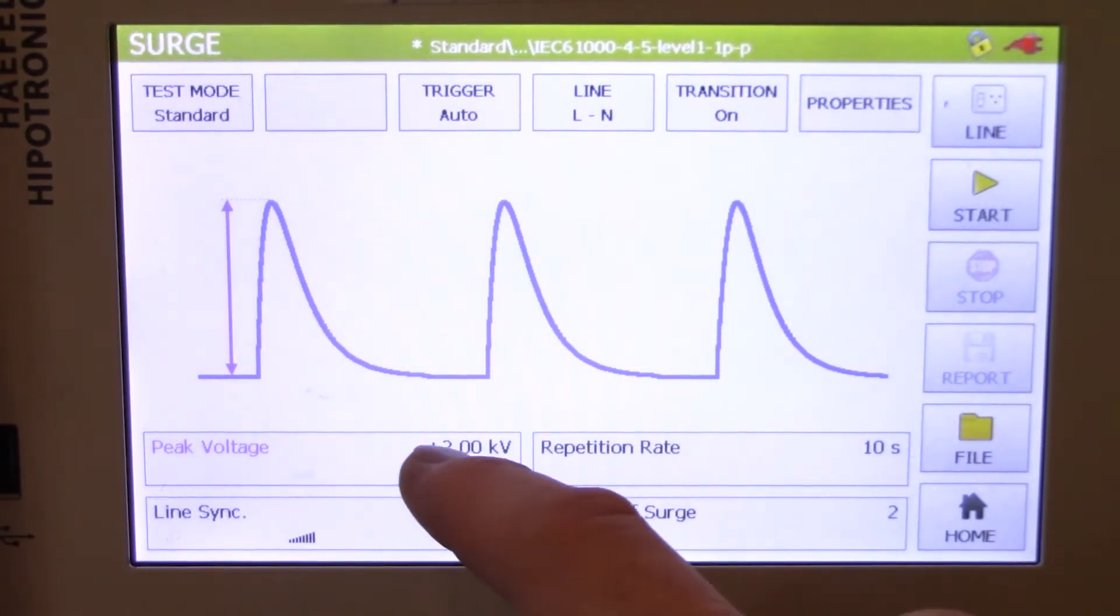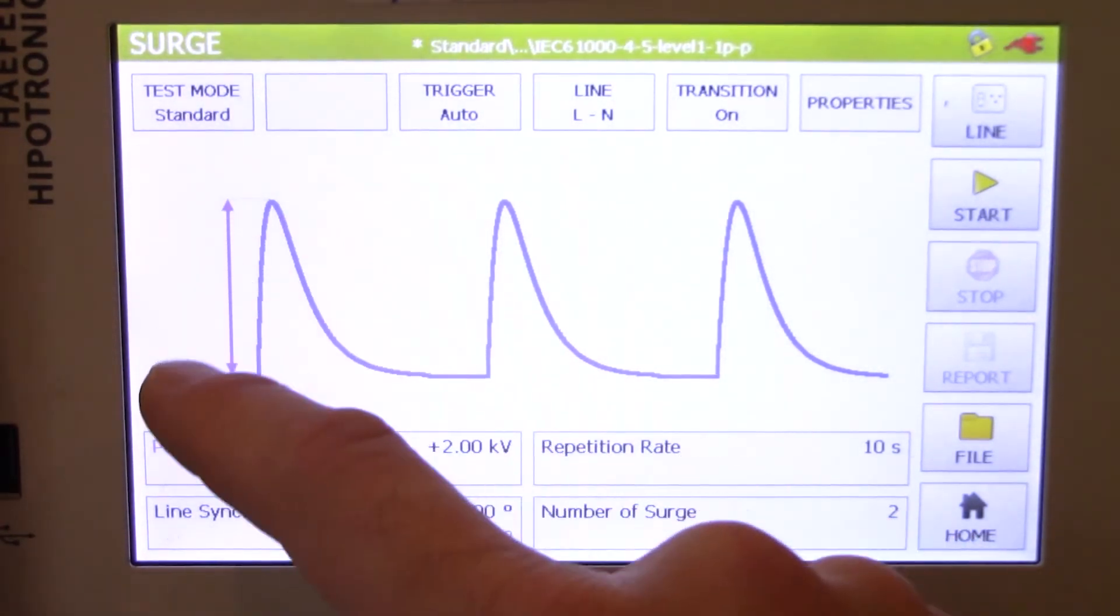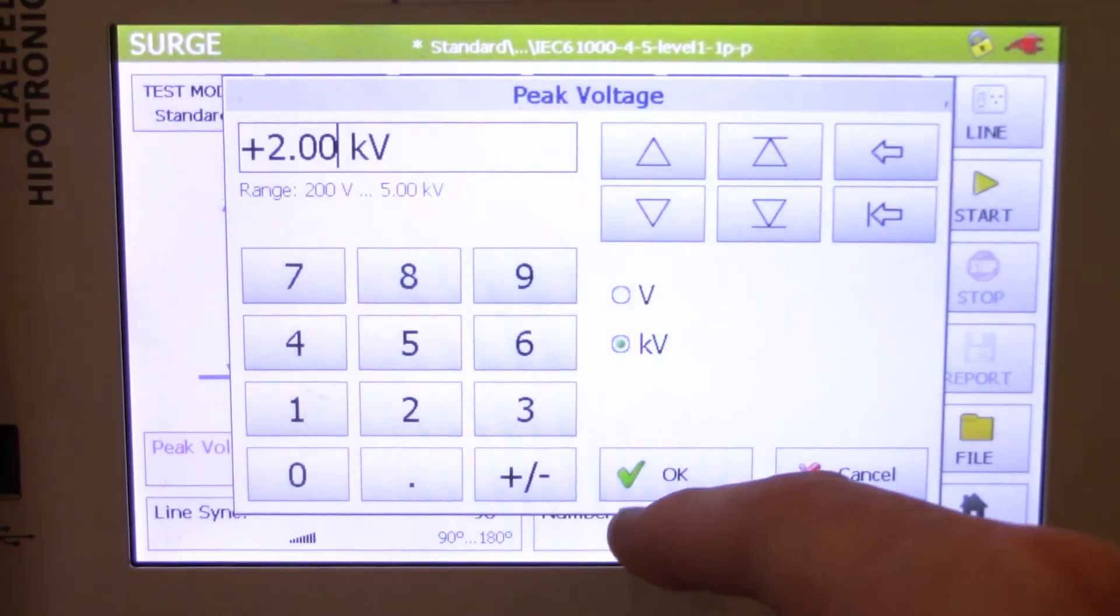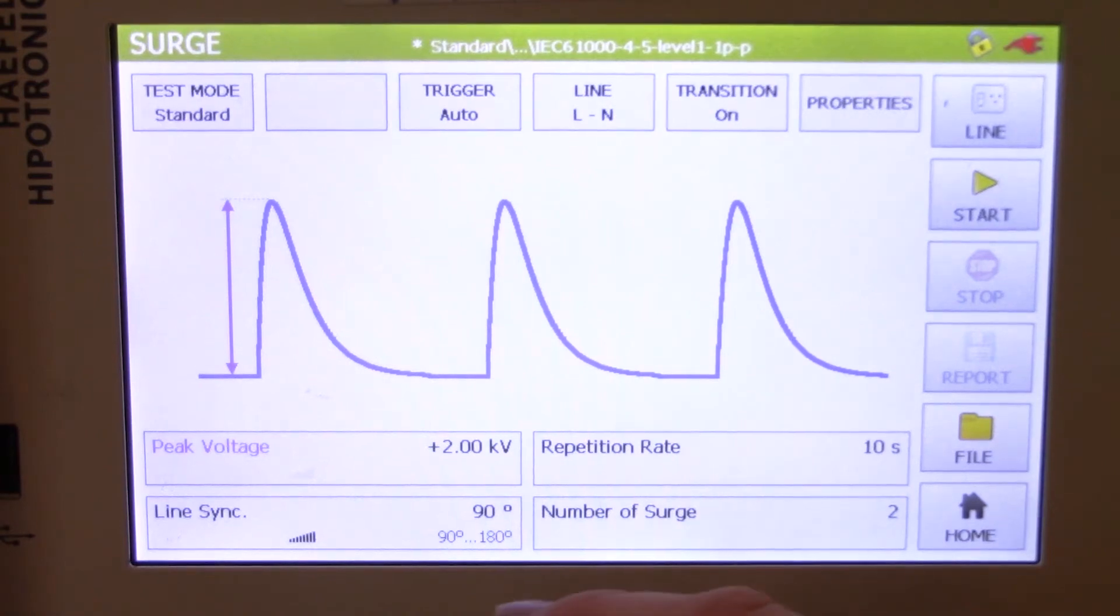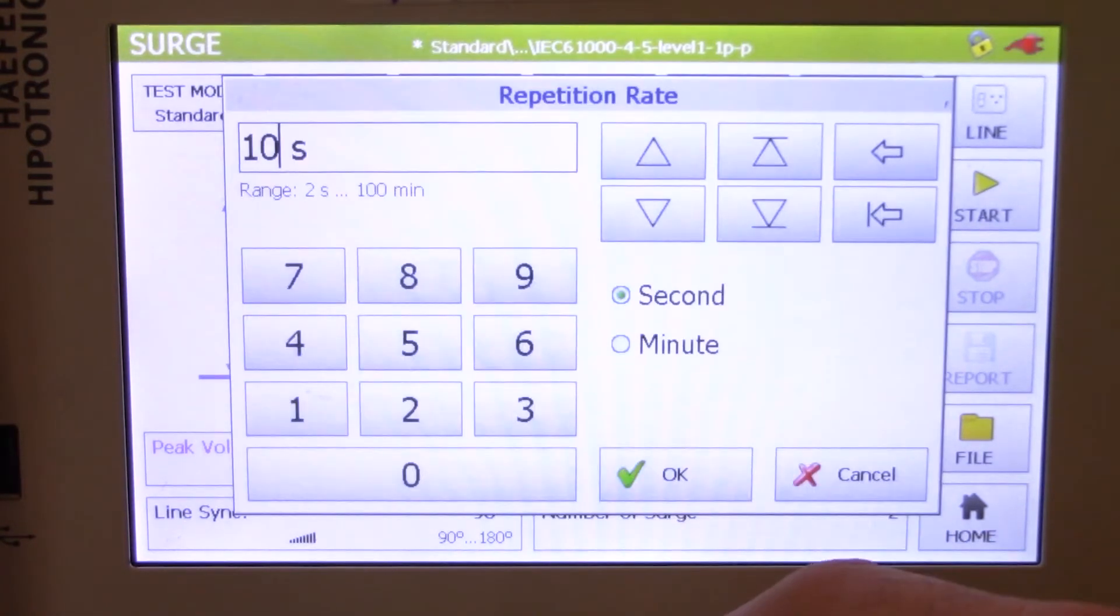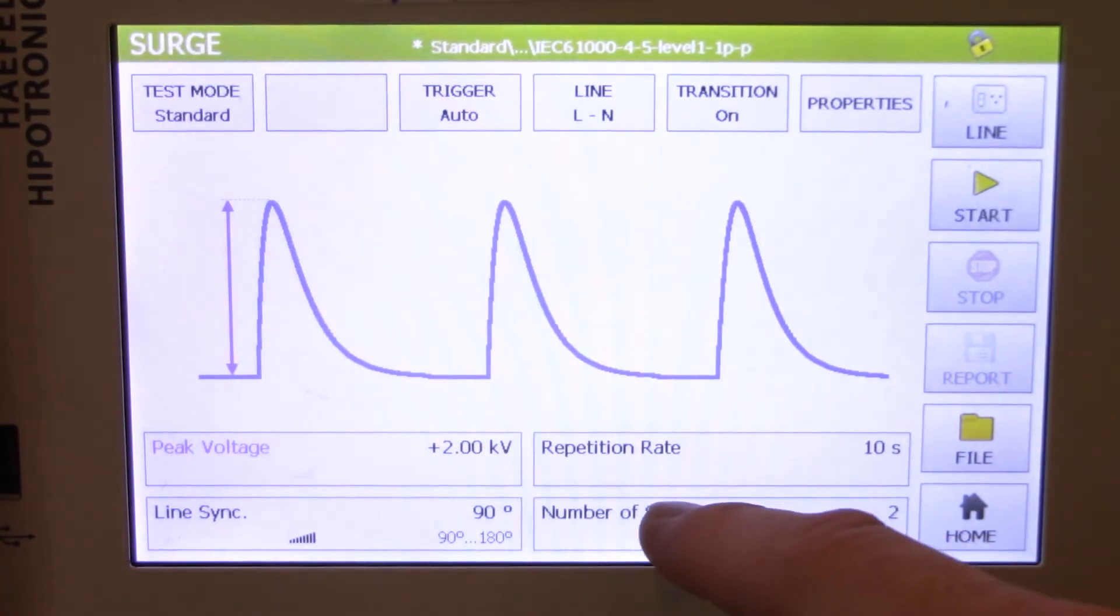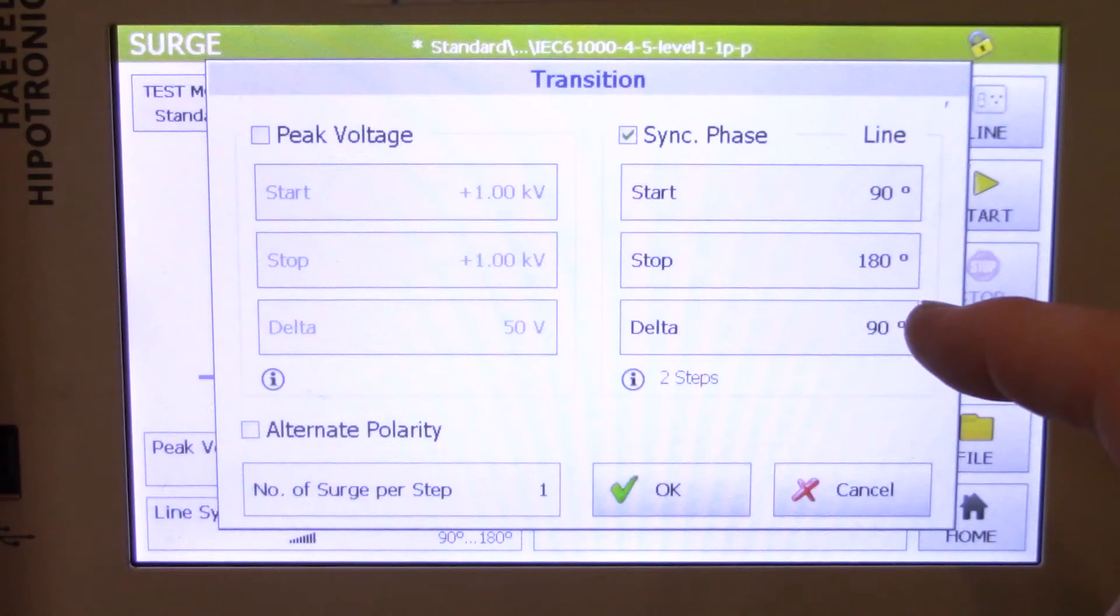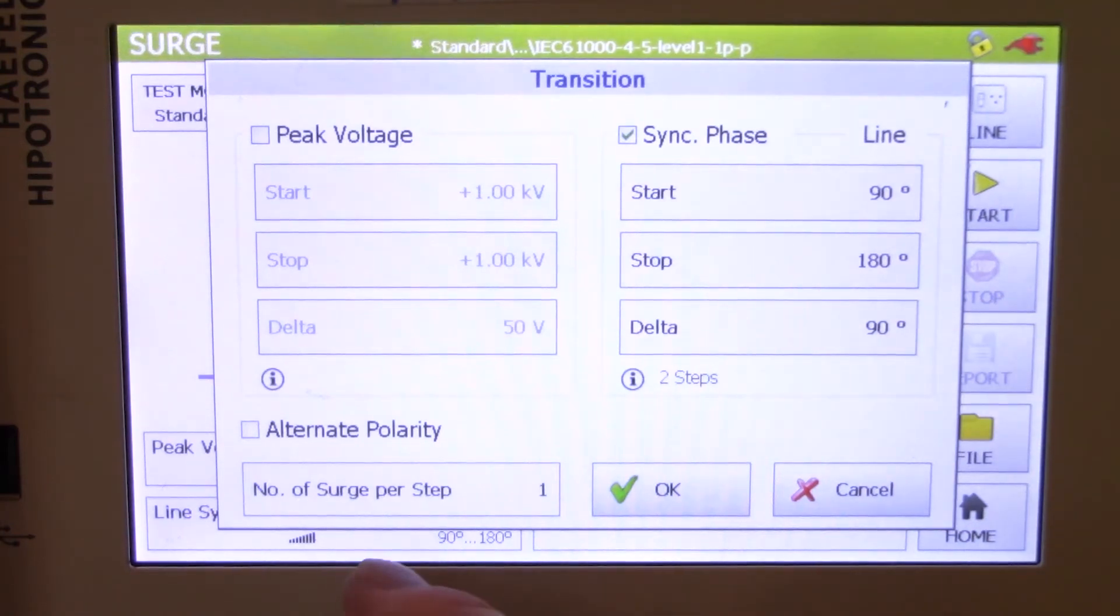One other thing you want to be aware of is your peak voltage. You'll see that indicated on the left side of the icon right there. You can adjust that. I think today we're happy with 2 kV. We'll go ahead and take a look at repetition rate, so we're just 10 seconds, number of surges. Click on that, you see the line synchronization right there, 90 to 180 degrees. Number of surges per step is one, so we're okay with that.